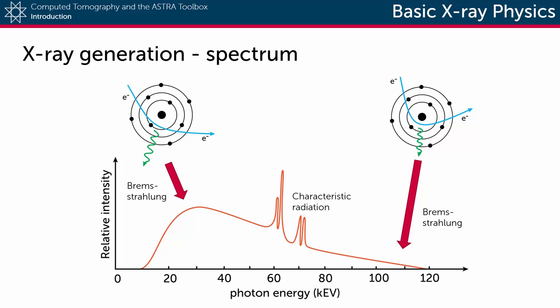Bremsstrahlung occurs when the electron slows down as it passes close to the center of the tungsten atom. The loss of energy is then converted to an X-ray photon and depending on the distance to the atom nucleus, this X-ray photon will then have a different energy resulting in an X-ray spectrum that is for example spread out between 10 to 120 keV.